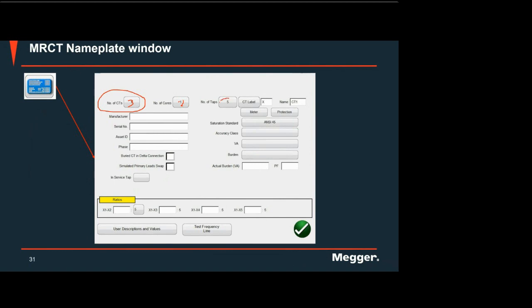You can also select the number of taps. Remember that the MBCT or the MRCT can do 5 simultaneous taps. You can change the label. You can put the name. You can select whether it is meter class, metering class, or protection class, the saturation standard, the accuracy class, VA, and the actual burden.